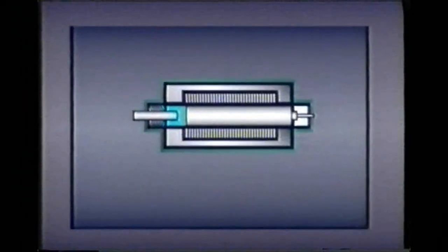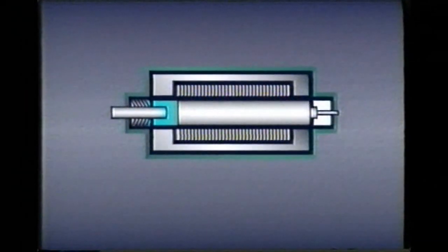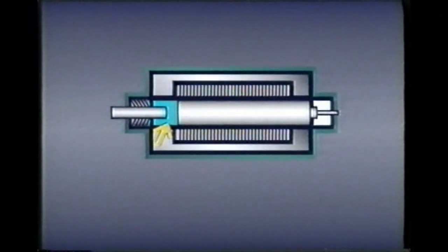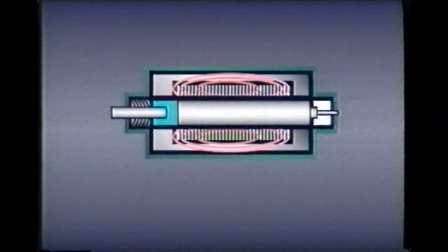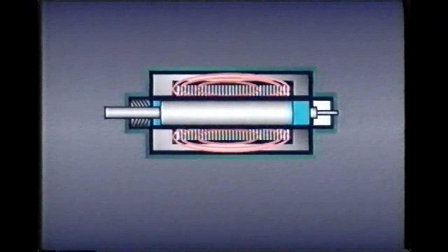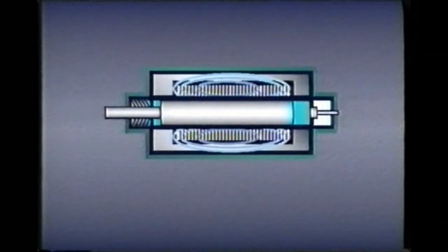Wet armature solenoids work similarly. However, the solenoid tube is screwed into the valve body and fluid from the system surrounds the plunger. When voltage is applied, high inrush current creates a strong magnetic field that pushes the plunger against the push pin. As with an air gap solenoid, current drops from the higher inrush level to the lower holding level as the plunger seats and shifts the spool.